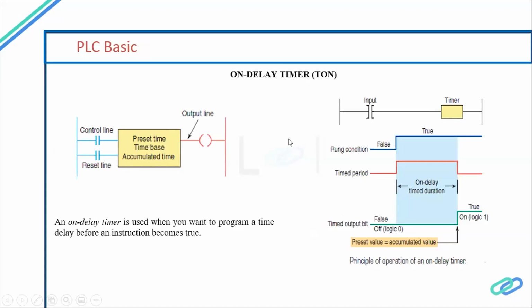So this is PLC basics for the on timer. I am giving you an example of the on delay timer. An on delay timer means if you give a command, only after the preset time do you get the output command. You do not get the output command directly. So some delay is there. Why is the delay required? Just like, say you have an HT motor, maybe 6 megawatt or 10 megawatt, for example a cement grinding motor. If you give a direct command while 2-3 more devices are taking start commands in parallel, and the drive starts automatically, then maybe your substation gets a huge jerk and cannot handle it, and the complete plant trips due to a lot of load variation.